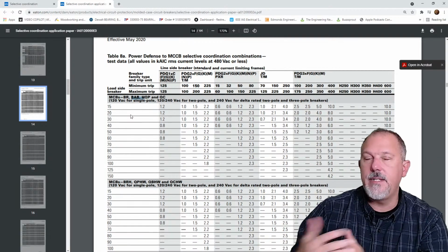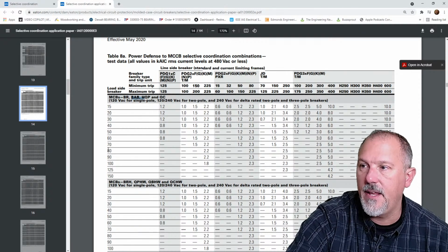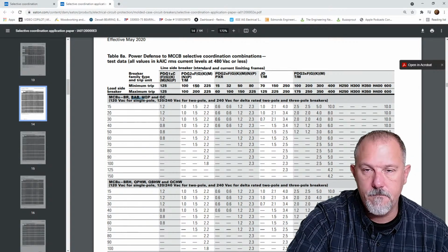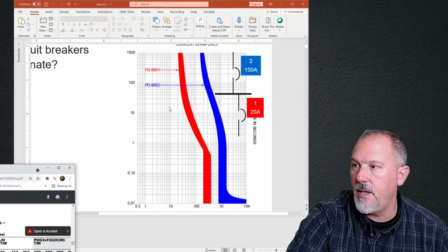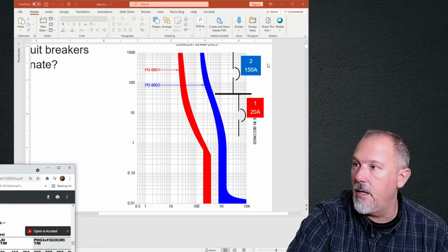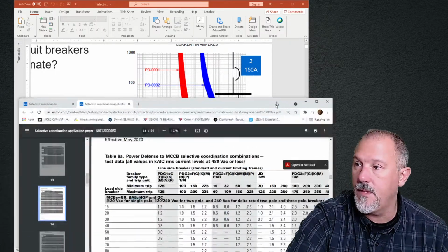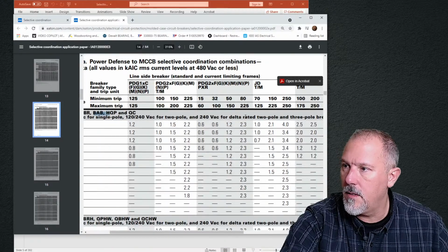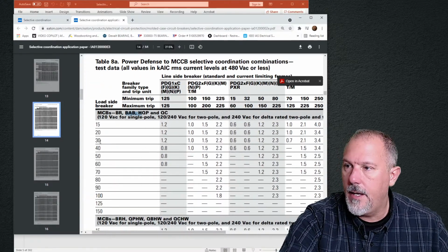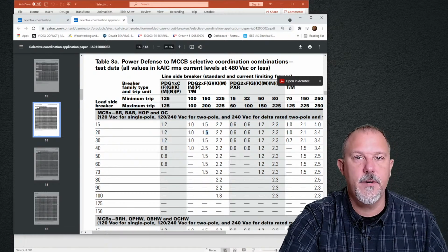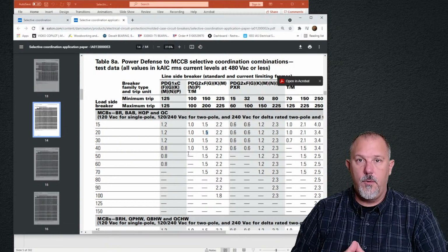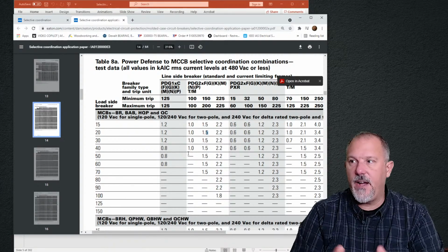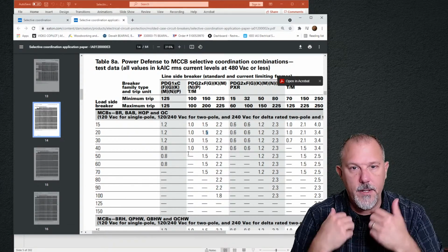And how you use these tables: these tables, tested pairs, they tell you that what's over here on the left-hand side is your downstream circuit breaker, and what's across the top is your upstream circuit breaker. So in our case, the downstream is this 20 amp BAB breaker, and the upstream is this F150, the circuit breaker, not the truck. I'm going to zoom in for you, and here's my 20 amp, and there's my F150, 1,500 amps. So I know if I had anything greater than 1,500 amps, both of these devices are going to open, right?